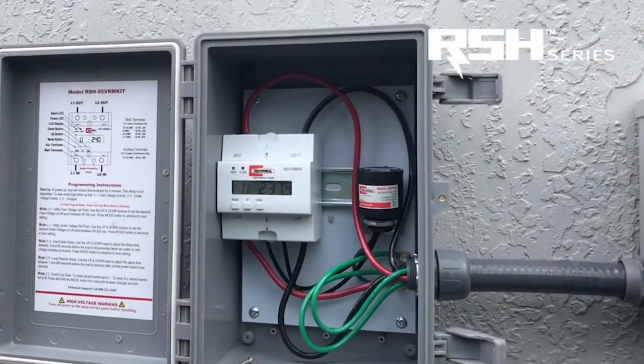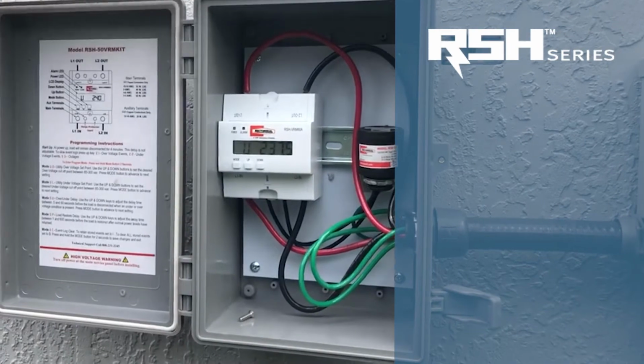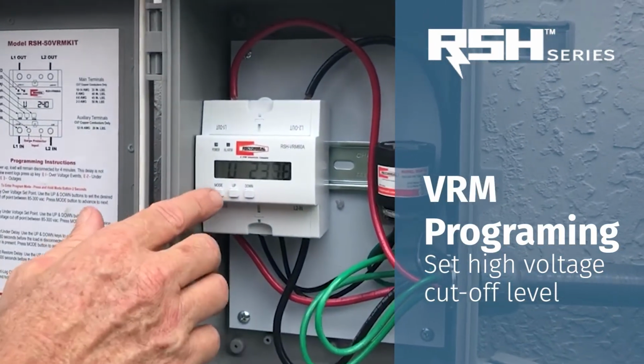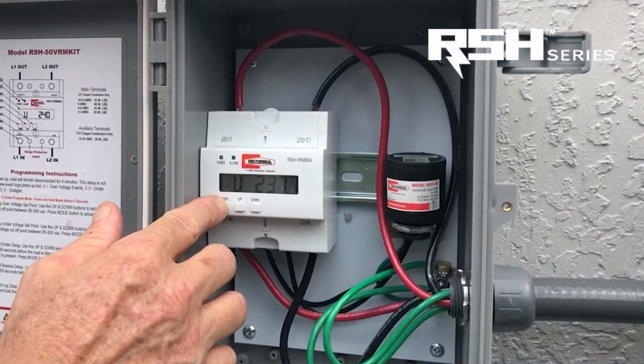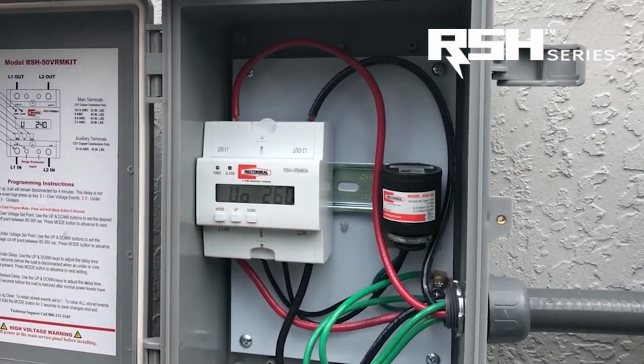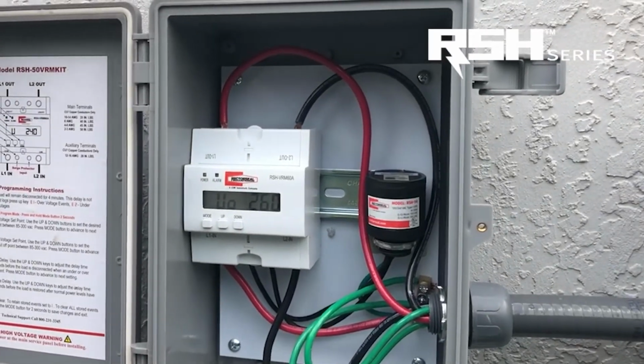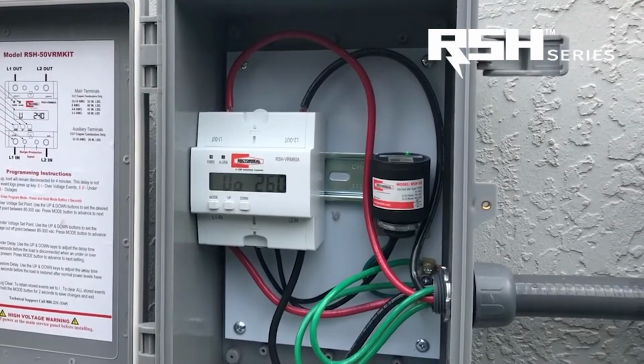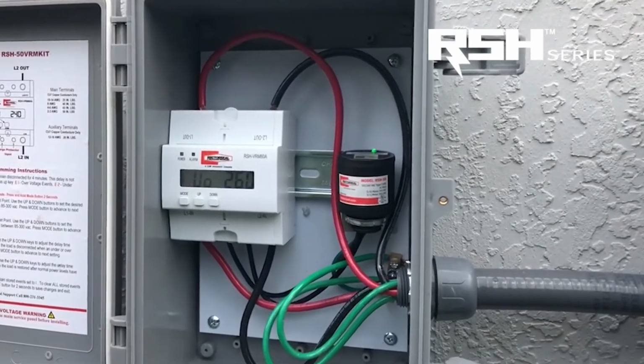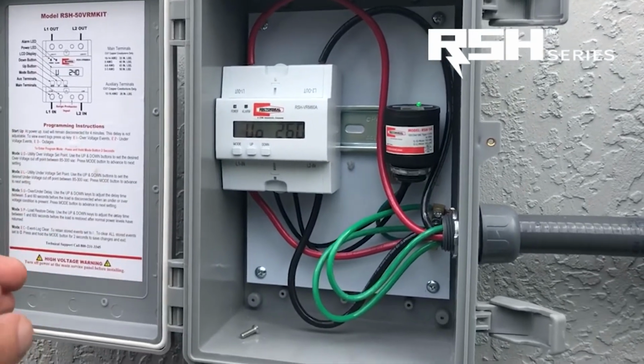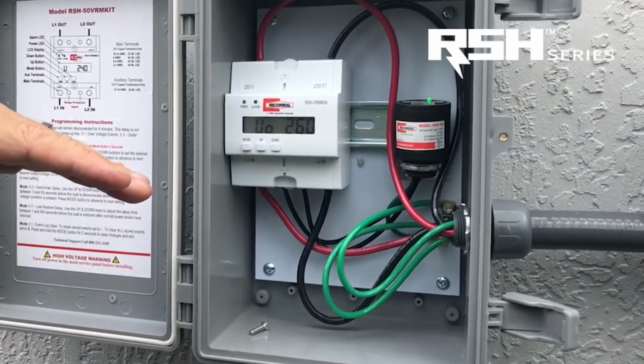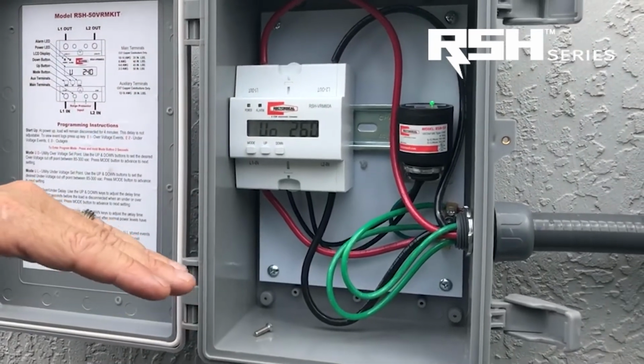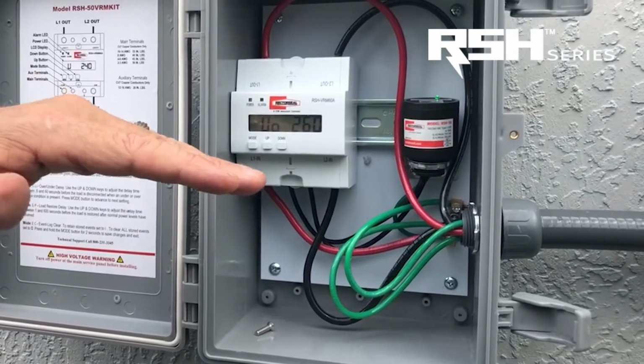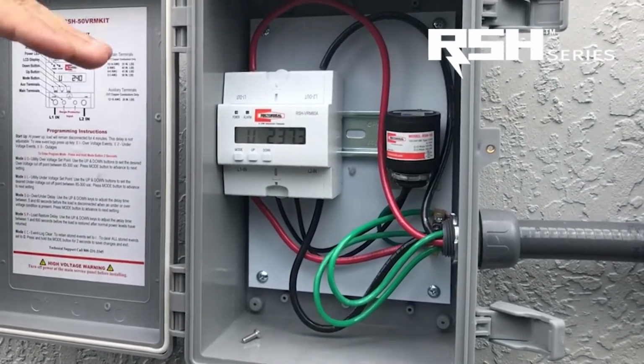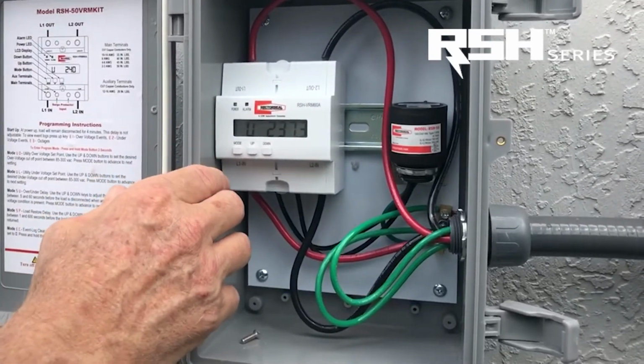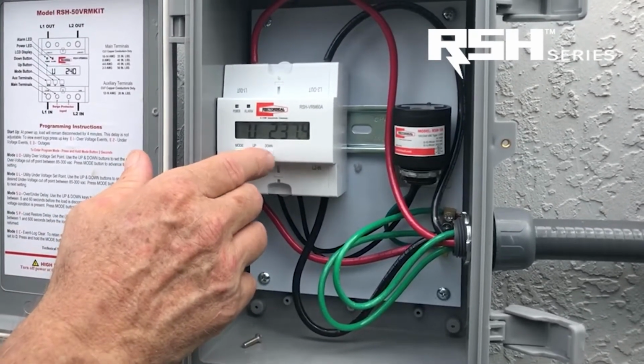So the first thing we want to do is set the cutoff at a high voltage or over voltage condition. And the way you do that is you just press this mode button and it'll take you to the option to set an over voltage cutoff point. And there's two schools of thought. One is use the manufacturer's suggested voltage range, or you can program it based on 10% above and below nominal voltage, which is what we're going to do here. But you have the option to program this from 90 volts up to 300 volts. So you can set your own range. But in this case, like I said, we're going to use the 10% above and below the nominal voltage level.